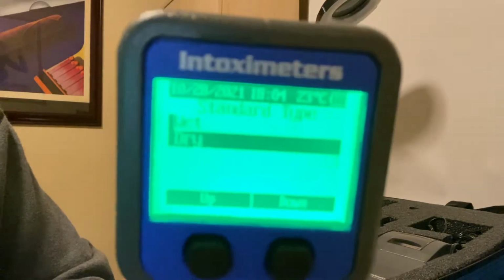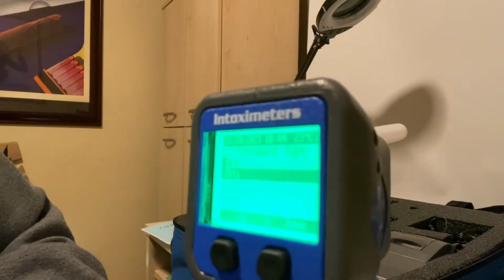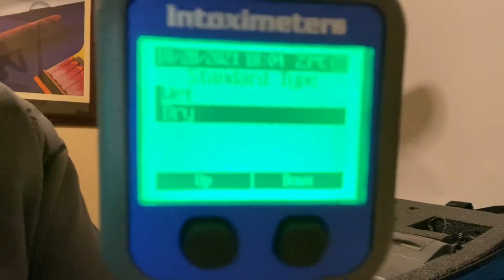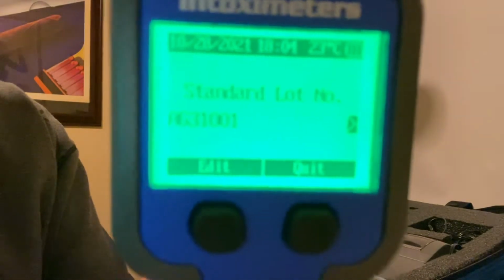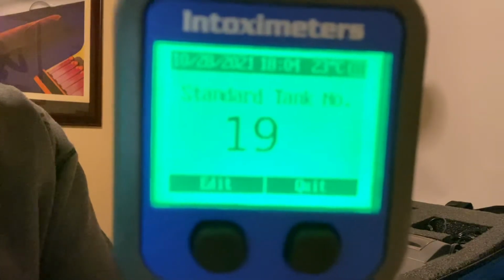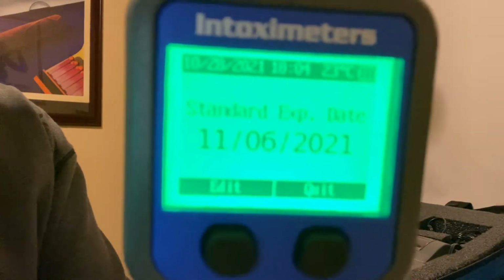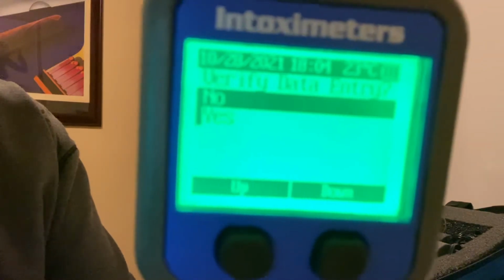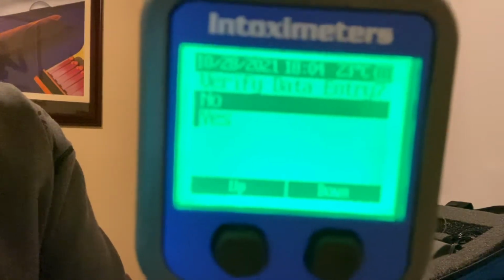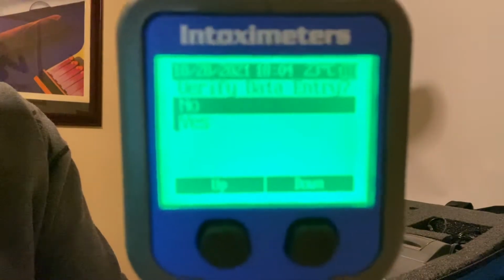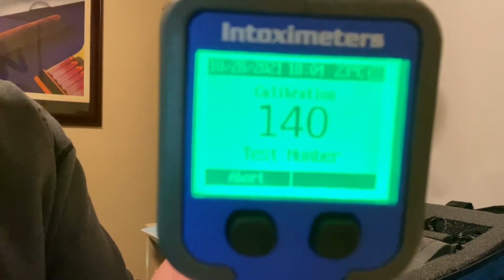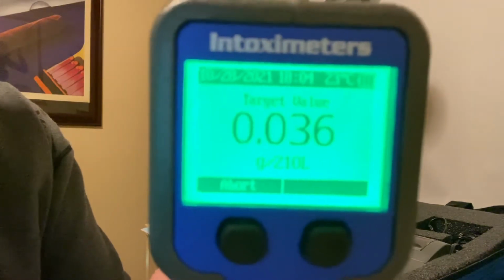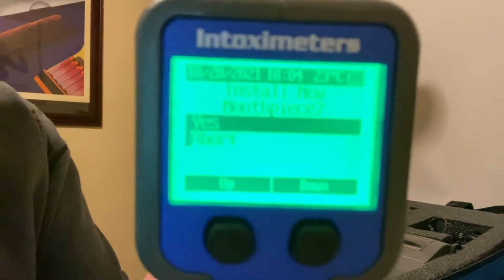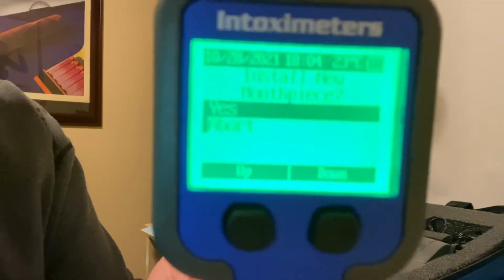I squeeze the trigger, and now it's asking me for the same type of information that it asked me in the previous one. Dry, all the information on the tank, and I'm just squeezing the trigger to go through everything, expiration date. And then if I needed to verify the data on the tank, I would hit yes, but I don't need to verify it, so I'm going to click no. And then this is going to be test 140, and my target is going to be .036. It's going to ask me to install the mouthpiece, which I've already done. So I'm going to pull the trigger and say yes, mouthpiece is installed.